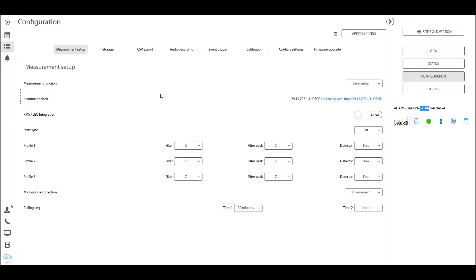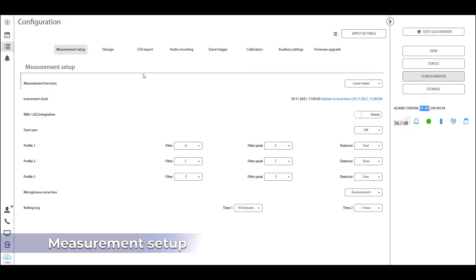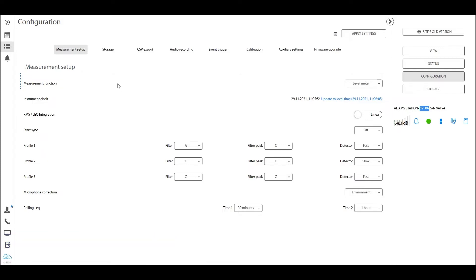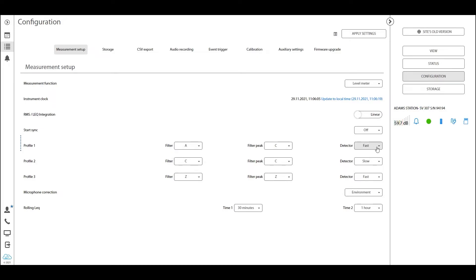We have all the panels organized up here in a very logical order. The measurement setup is the tab that is a ruling or master tab that will affect all of the other tabs. In here, you will most commonly be changing profile one, two, or three, where you can set the different acoustic weightings between A, Z, and C, as well as the time integrators.